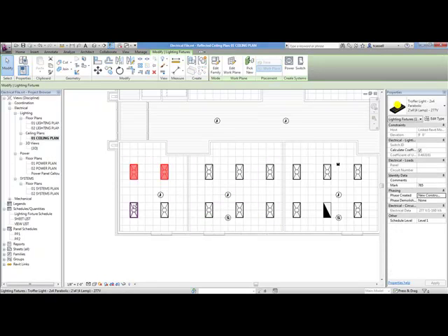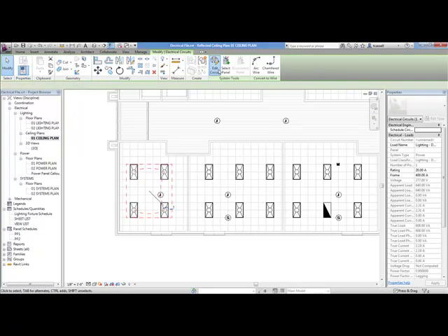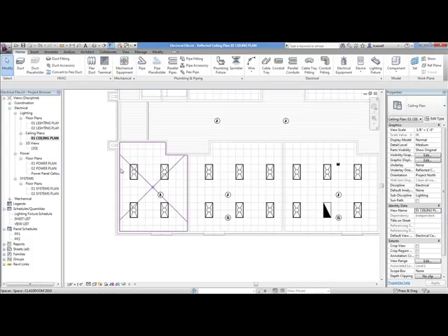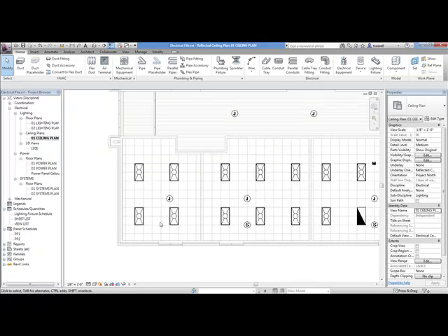We'll take the other room and we'll put it on the next circuit. So we'll create another power circuit, again showing how fast it is to do this. Put it on LP1 as well, and a 0.83 volt drop, 10 gauge wire. Let's put it on THWN, 12 gauge wire, 308 feet because this is a little further away. Since we have a higher gauge wire, it's going to be a slightly higher voltage drop. Let's finish that as well. So now that these are circuited, we'll go look at the panel in just a minute.